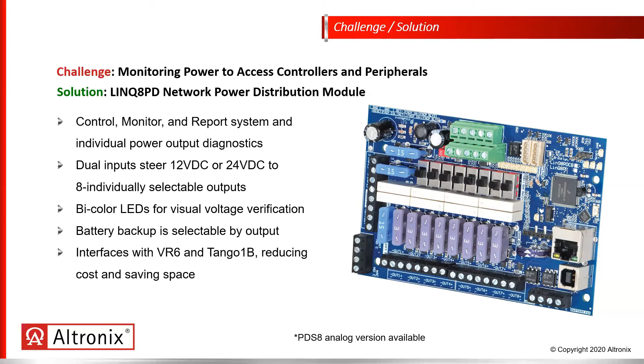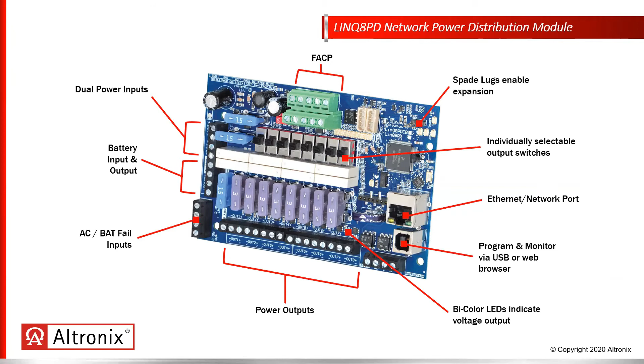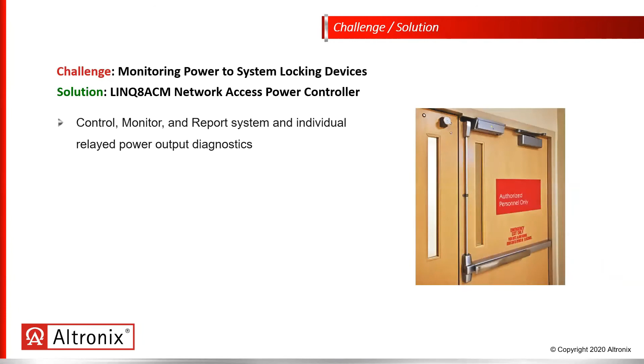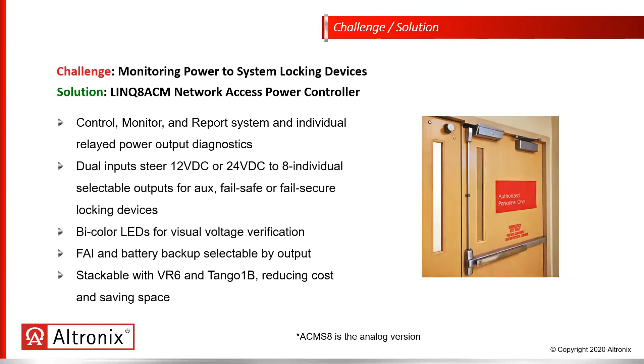And from the field, the technician can see, using the bicolored LEDs, visual verification of which voltage is directed to which output. We have further ability to choose our battery backup, selectable by output. And this device is going to make monitoring each individual output very simple. You'll notice here, I want to note the spade lugs, upper right-hand corner. There are spade lugs on the board, which allow us to deliver both 12 and 24 volts DC to additional sub-assemblies that might also be in the enclosure. So a single 24 volt power supply, giving us 12 and 24 volts DC across multiple outputs.